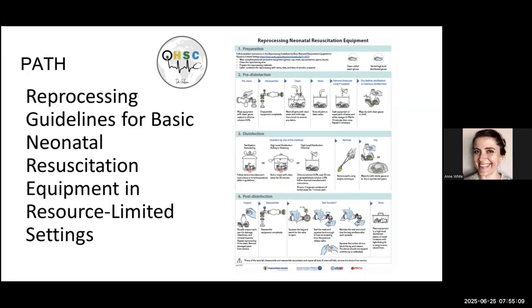The second stage is called pre-disinfection, also known as the cleaning stage. That is when you physically wipe down the outside of the equipment. They disassemble it and scrub it with some soap and water, and again, they're trying to get rid of the blood and the meconium. And even if you can't see any of those things on the equipment, the first step needs to be cleaning it, to remove anything exterior that will interfere with the disinfection.